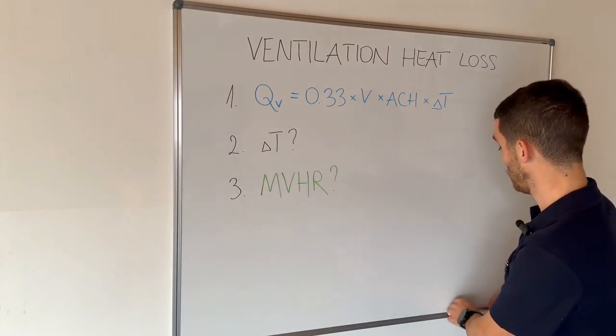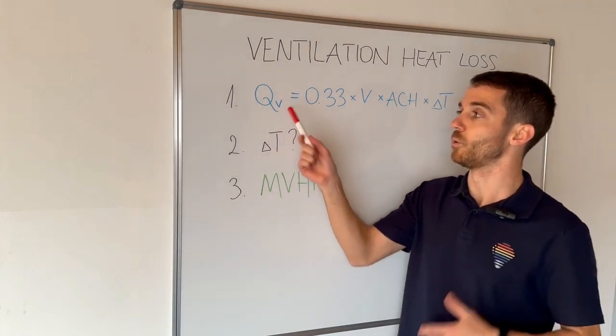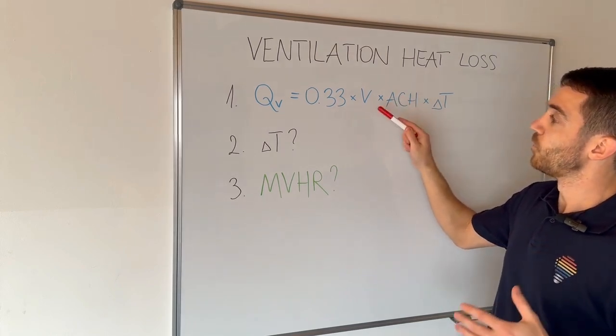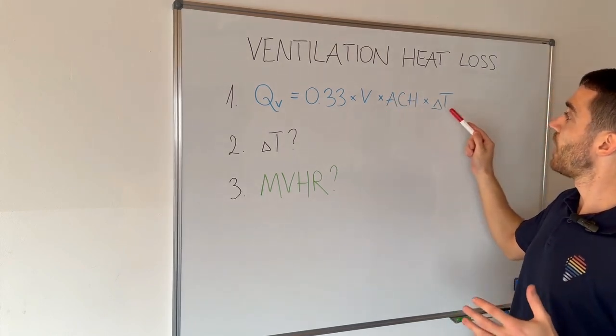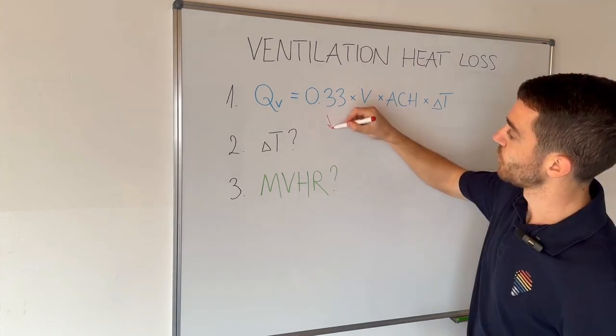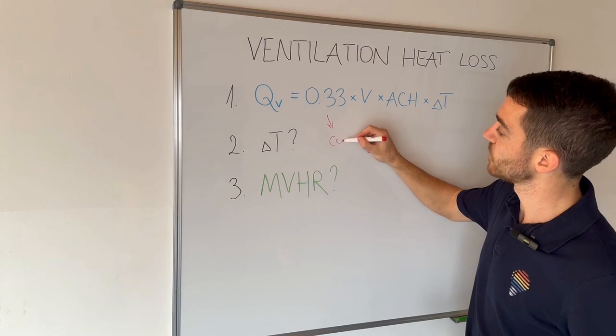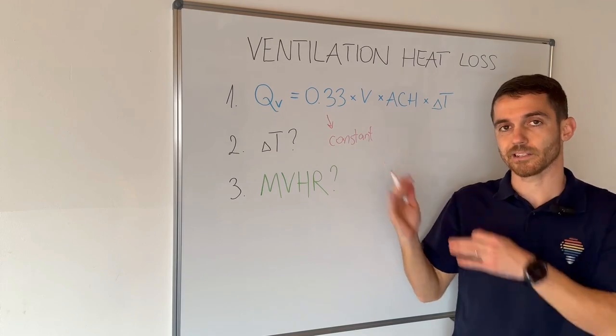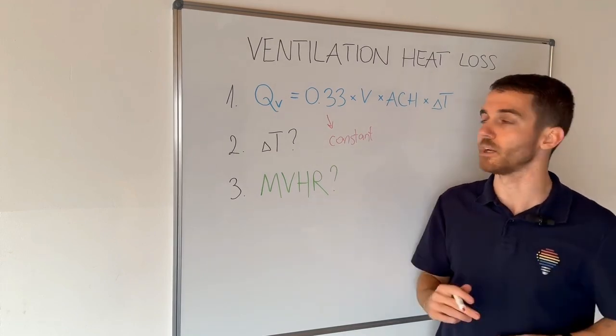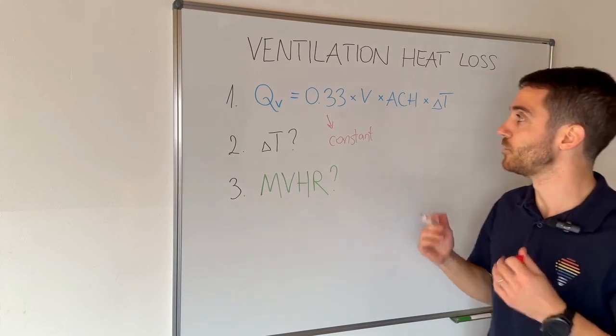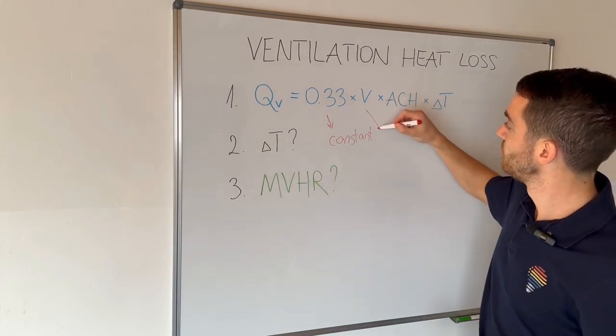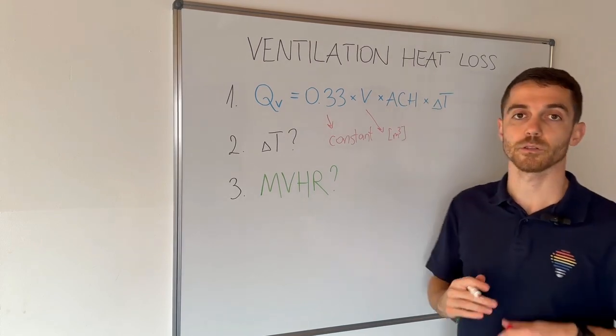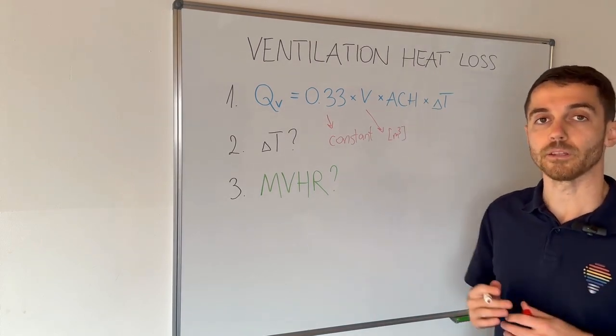Let's start with the formula. Q ventilation equals 0.33 multiplied by volume, multiplied by air changes per hour, multiplied by delta T. The constant 0.33 relates to the density of air with some values calculated inside, but we treat it as a constant in the formula. Volume is our volume in cubic meters — surface area multiplied by height.